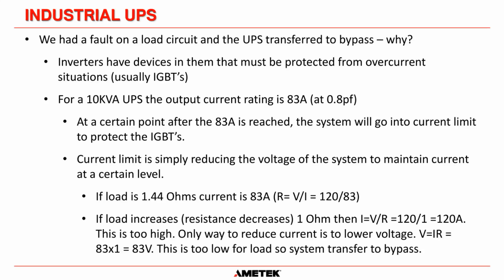So if we buy a 100 amp IGBT, we want to make sure that the current doesn't go above 100 amps through that IGBT. So for a 10 kVA UPS, the output current that we say out of the system at 0.8 power factor is 83 amps. So at a certain point after the 83 amps is reached, the system will go into current limit to protect the IGBTs. For ease, we'll say in this 10 kVA UPS, 100 amp IGBTs were used. So we want to make sure that anything above 83 amps, we start limiting the current, because we don't want to get close to this 100 amps that could blow up an IGBT.